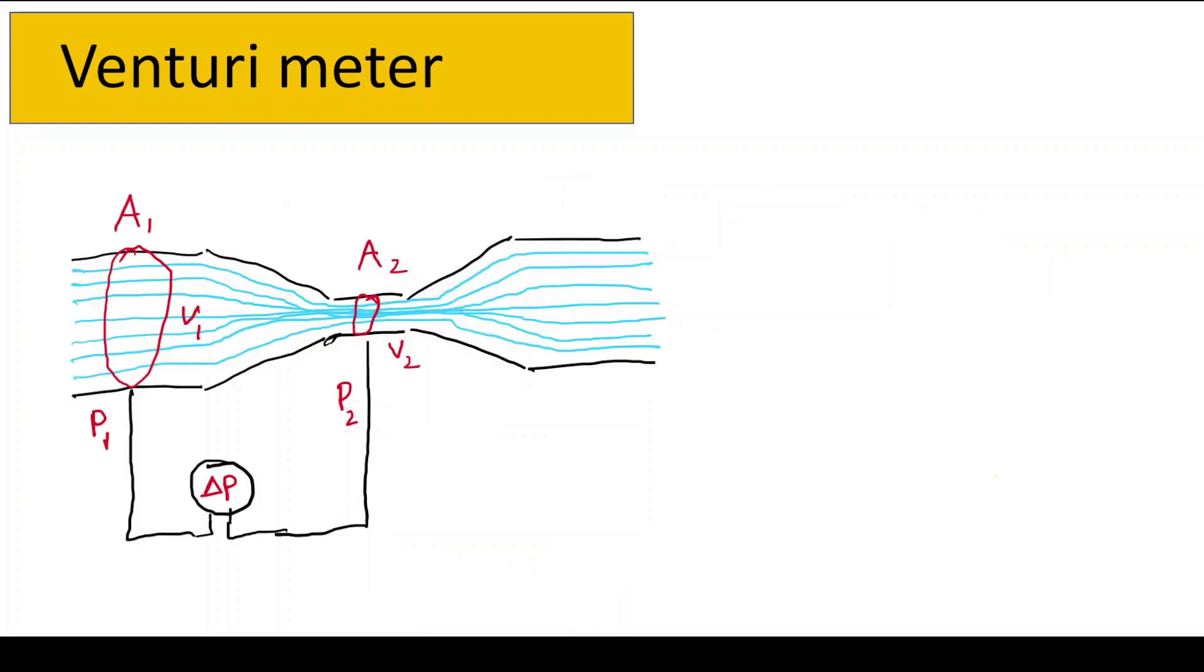Well, when the fluid flows through the venturimeter, it encounters the narrowing section, that is the throat area. According to Bernoulli's principle, as the fluid's velocity increases in the constricted section, its pressure decreases. So this pressure drop across the venturimeter allows us to measure the flow rate. The pressure difference is typically measured using pressure taps or ports located before the venturimeter.